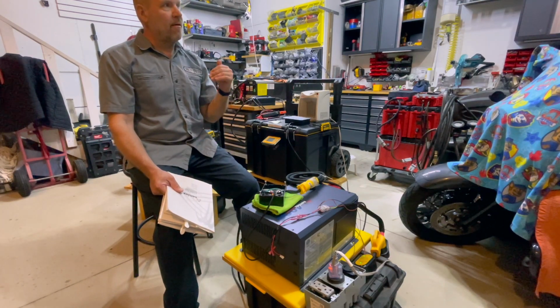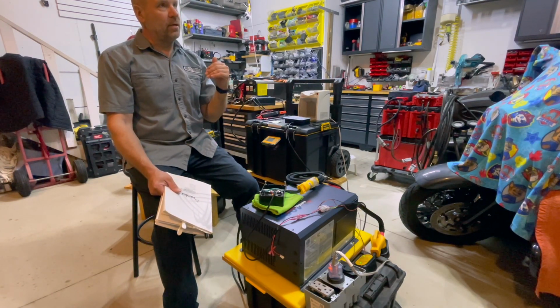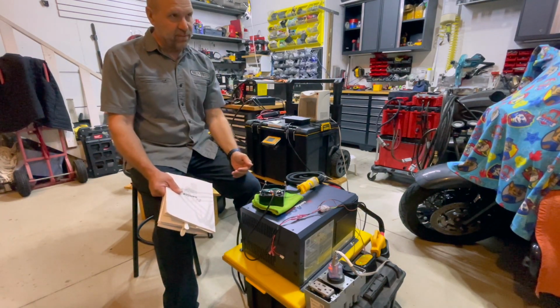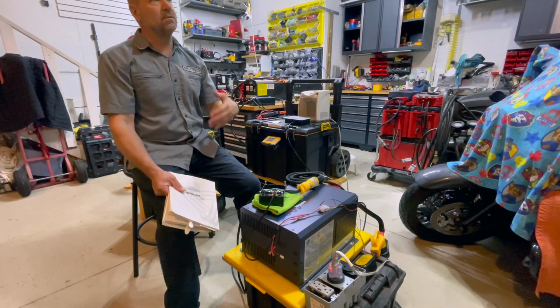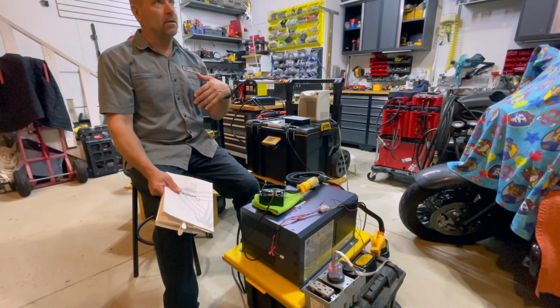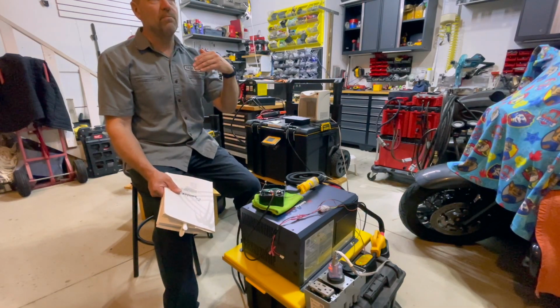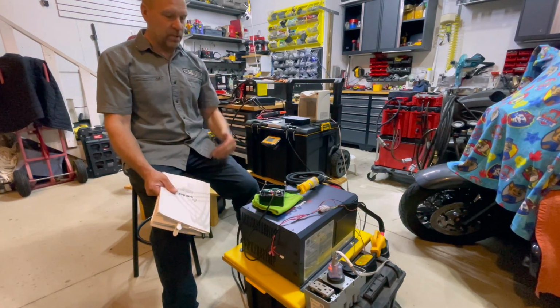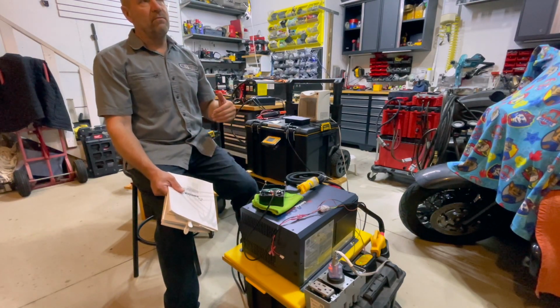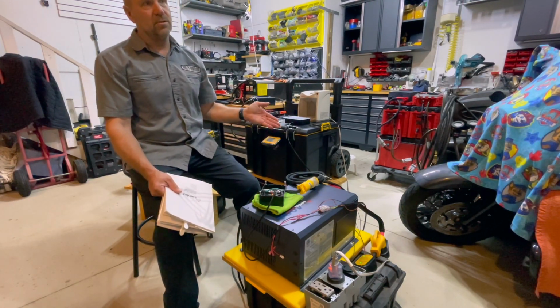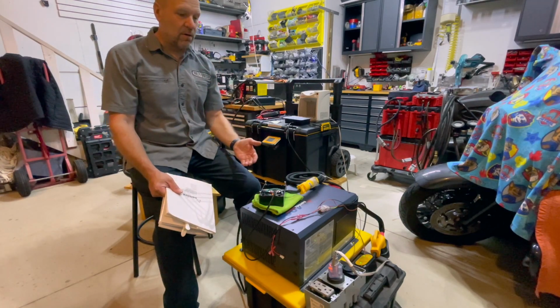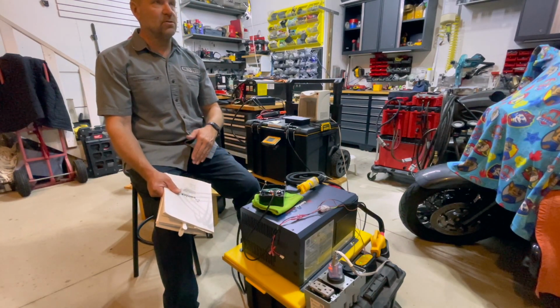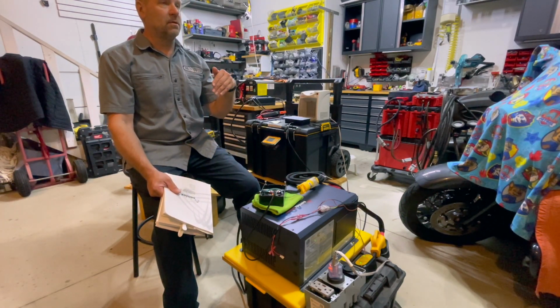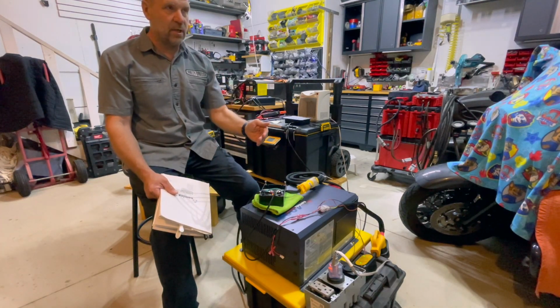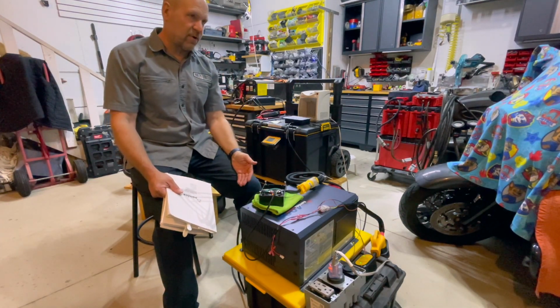It's turning off because you're using more power than you're putting in. Then the inverter, after a few minutes, turns itself back on, because again it still sees the AC source, and it tries to handle the load again, and then it shuts itself off.